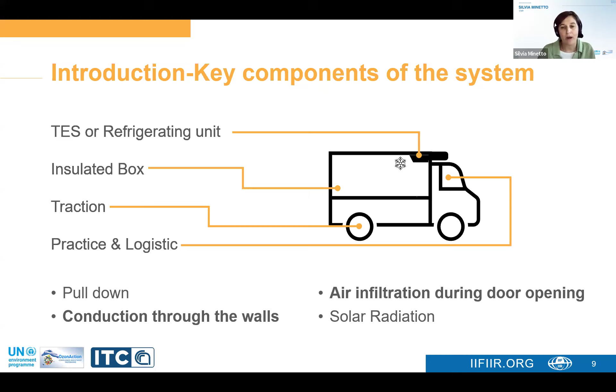We can first talk about the conduction heat load. So what comes from the walls of the box when the box is closed. And this is typical of, for example, long distance transportation. The insulation capability of the box is typically described by the K value. K is the symbol which is used in the ATP, which is the Agreement on the International Transport of Perishable Foodstuff. But this is also identified with U widely in the literature. It's the overall heat transfer coefficient. The conduction heat load depends from the temperature difference between outside and inside. So if we move from 30 to 50 degrees, we can see that the thermal load increases by, in the worst case, which is the case in which the box is at 0 degrees, it increases by near 70%.